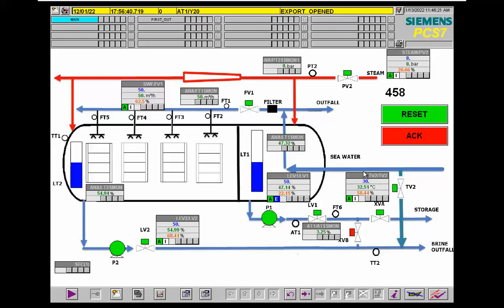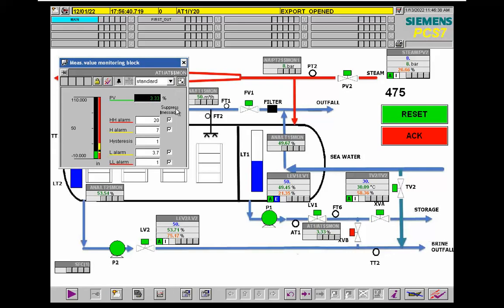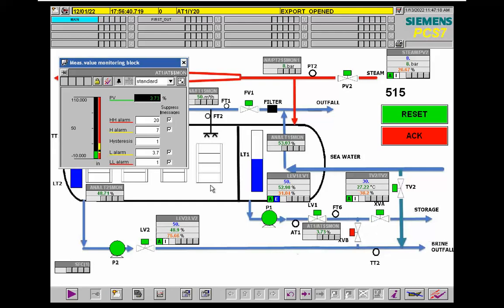Ideally the plant will work on all these set values, and you can see that this valve is transferring the product to storage in case of having a suitable conductivity value. When we are in the safe region — less than 3.7 — it is safe to send the product into storage. We consider a hysteresis value of one to avoid frequent switching of this valve, so the low limit is 3.7 and the high limit is 7.